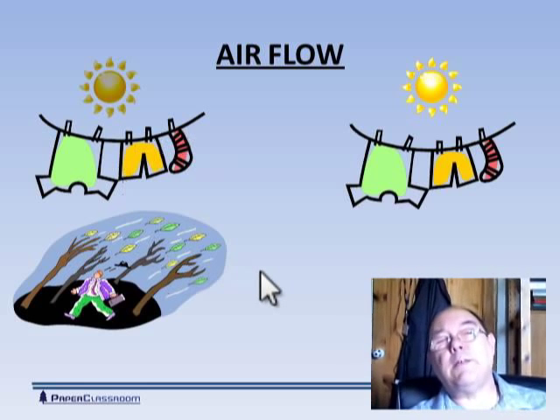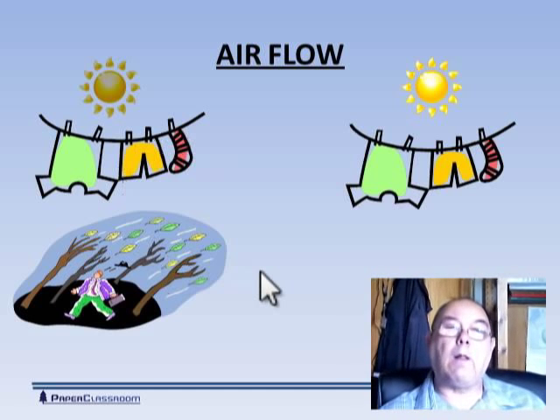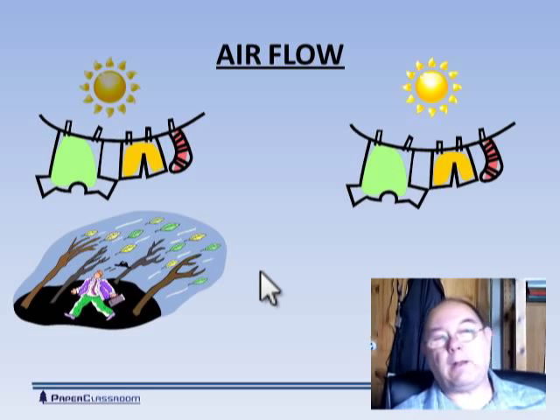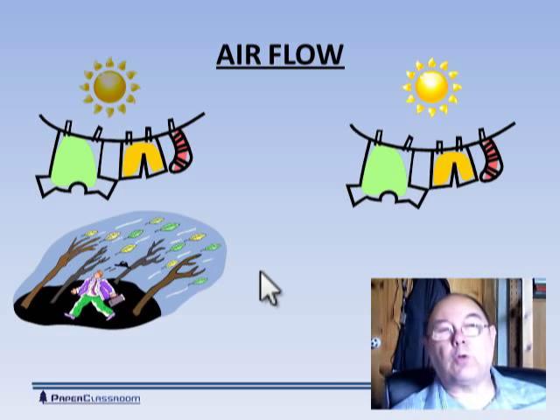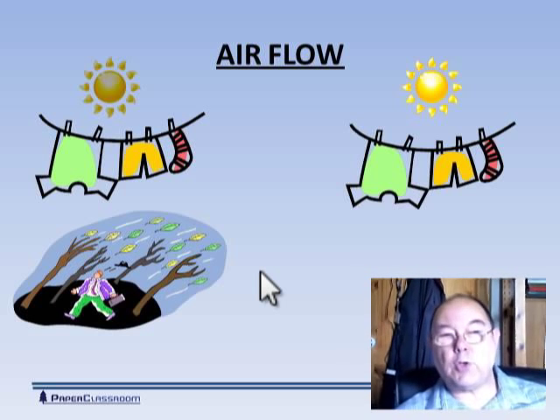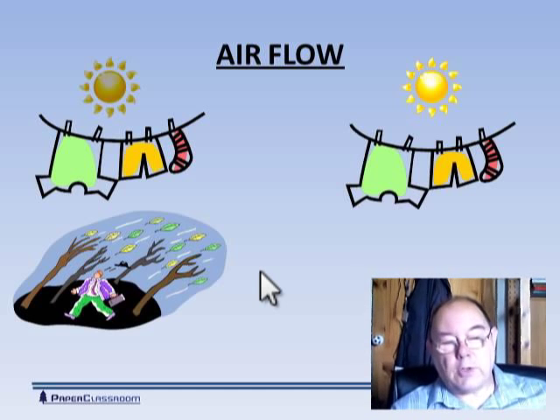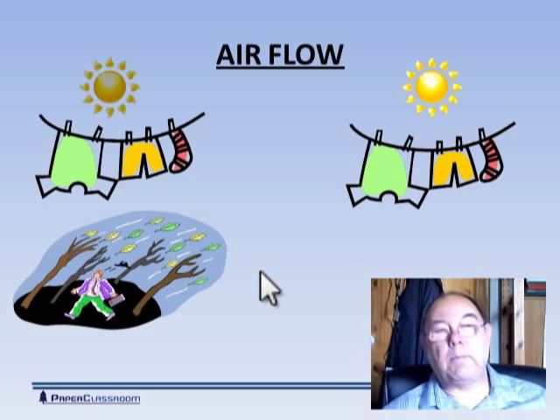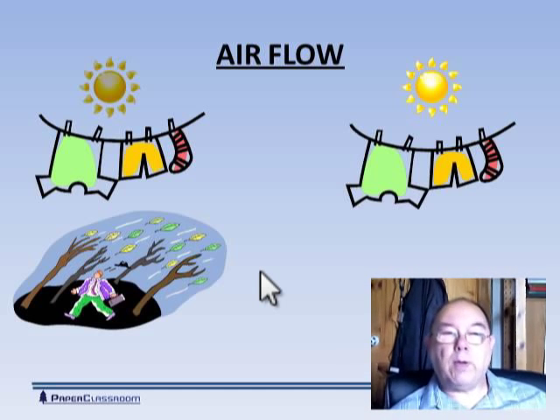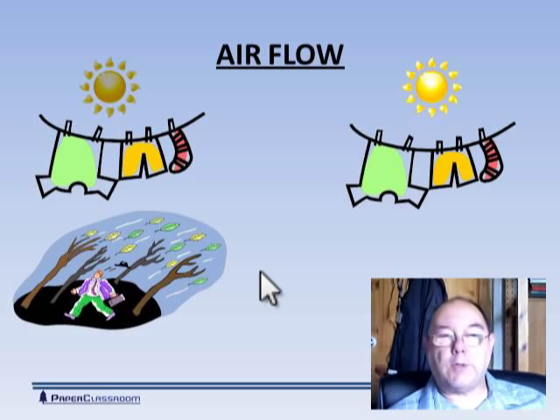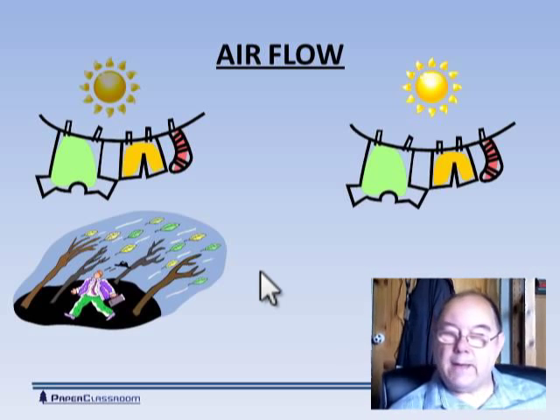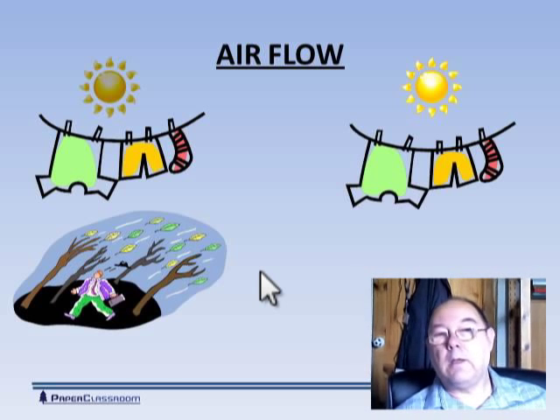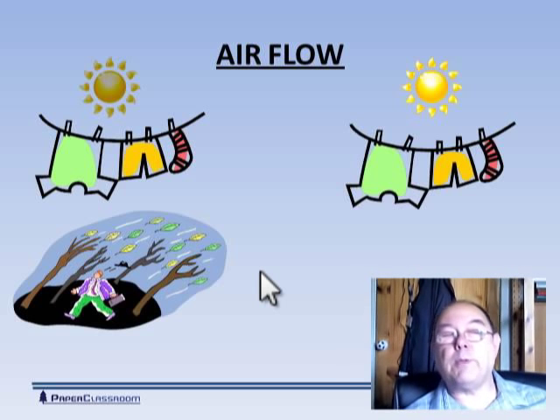Paper makers eventually realised this and started to enclose the machines. If you look at a modern paper machine now, it's completely enclosed. We have total control of moisture coming into the drying section area and air and moisture coming out. What we tend to do is bring in hot, dry air to push out hot, moist air. The hot, moist air passes through a heat exchanger, and that's how we heat up the incoming air.